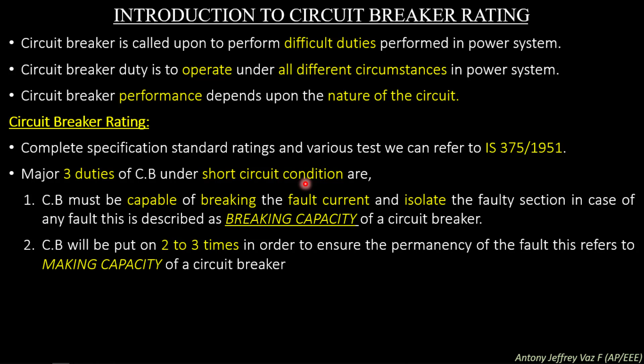The second one is making capacity. The circuit breaker will be switched on 2 to 3 times in order to ensure the permanency of the fault. This refers to the making capacity of the circuit breaker. If a fault occurs, then in a substation they will turn on the circuit breaker 2 to 3 times to ensure the permanency of the fault. If we turn on a circuit breaker onto a fault, then the peak current will flow through the circuit breaker. So we should ensure that the making capacity of the circuit breaker is up to the peak level which will flow in the circuit during a short circuit. So this is the making capacity of the circuit breaker.